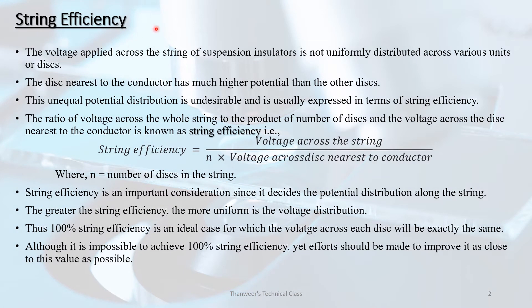String efficiency: what is string efficiency? The voltage applied across the string of suspension insulators is not uniformly distributed across the various units of disk suspension insulator. The disk nearest to the conductor has much higher potential than the other disks. This unequal potential distribution is undesirable and is usually expressed in terms of string efficiency.